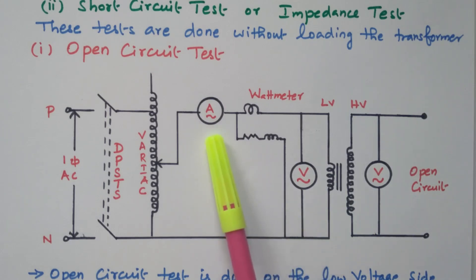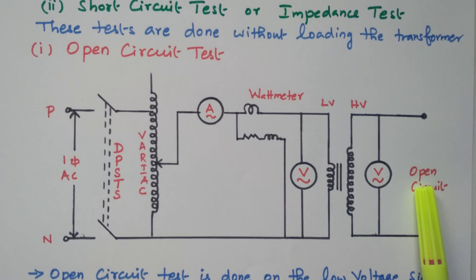The ammeter measures the no load current, the voltmeter measures the primary rated voltage, and the wattmeter measures the no load input power given to the primary. Since there is no load, the current flowing is very small, so we can neglect the copper loss. The power given to the primary winding refers only to the iron loss — there is no copper loss because only a negligible amount of current flows through the winding. The wattmeter reading therefore represents the iron loss of the transformer.